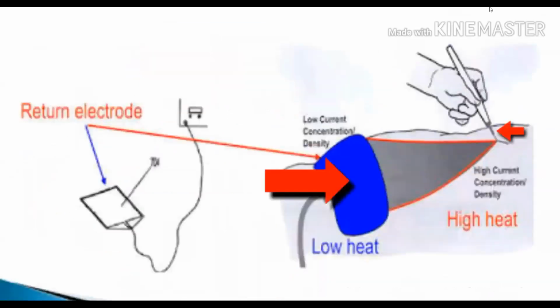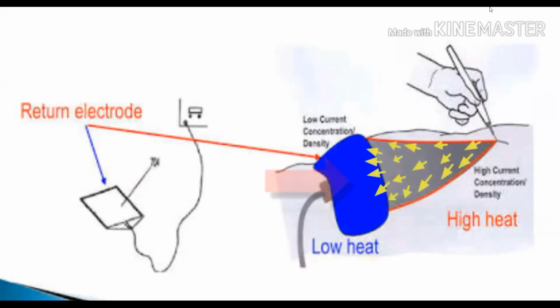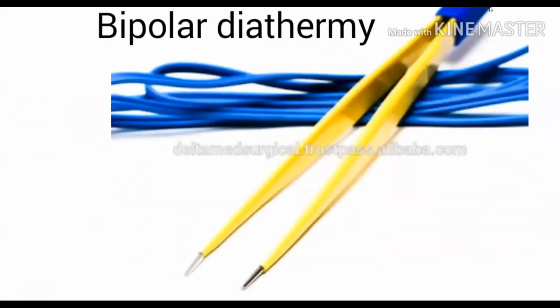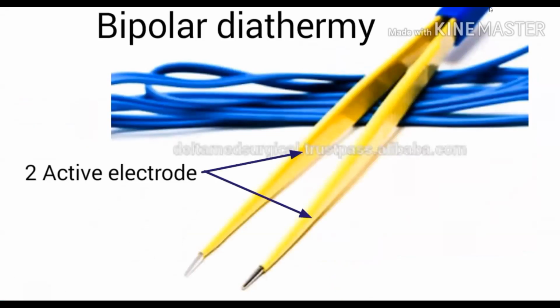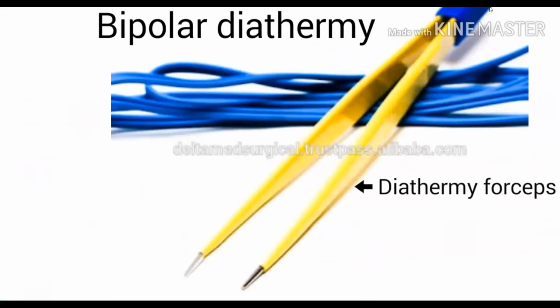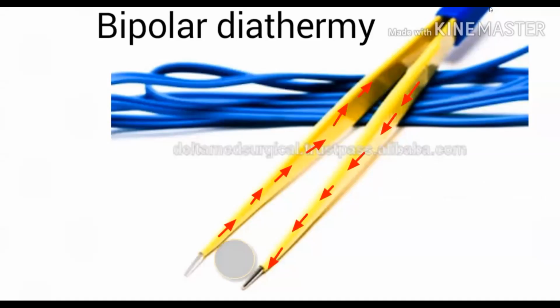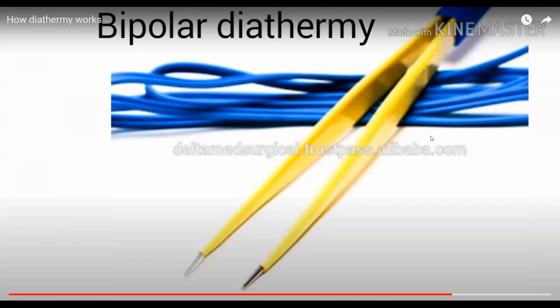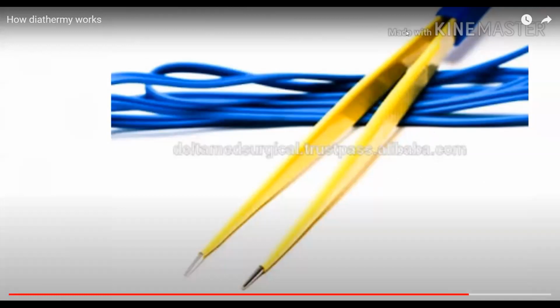As the surface area of contact of the active electrode is small in comparison to the passive electrode, the concentrated powerful current produces heat at the operative site. However, the large surface area electrode of the patient plate spreads the returning current over a wide surface area, so it is less concentrated and produces little heat. In bipolar diathermy, the two active electrodes are usually represented by the limbs of a pair of diathermy forceps. Both forceps ends are therefore active, and current flows between them, and only the tissue held between the limbs of the forceps heats up. This form of diathermy is used when it is essential that the surrounding tissues should be free from either the risk of being burned or having current pass through them.